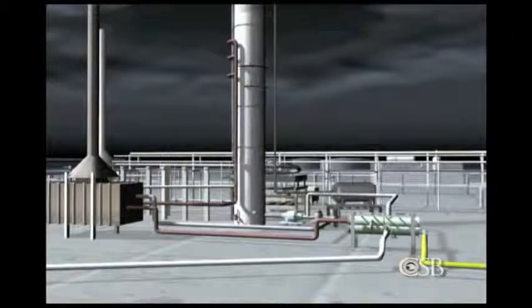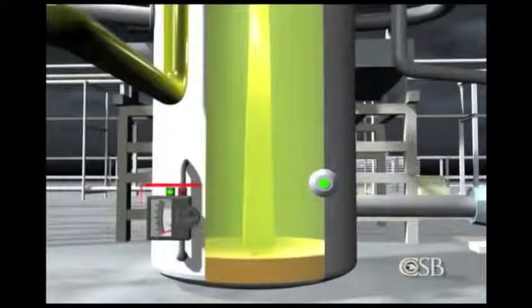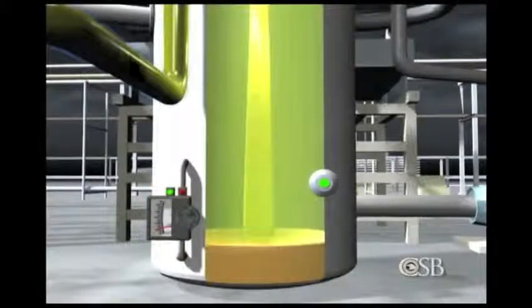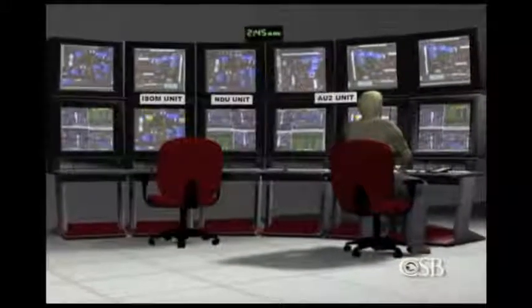At 2:15 a.m. on March 23rd, overnight operators began introducing flammable liquid hydrocarbons, known as raffinate, into a 170-foot tall raffinate splitter tower used to distill and separate gasoline components. Near the base of the tower, there was a single instrument that measured how much liquid was inside. It transmitted this information to a central control room located away from the ISOM unit.